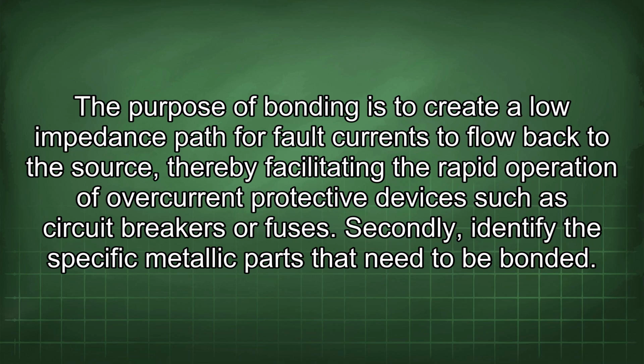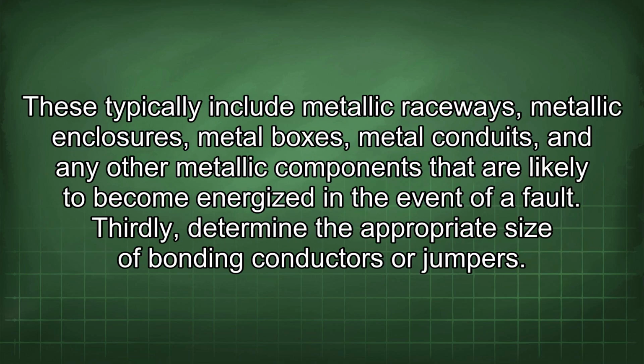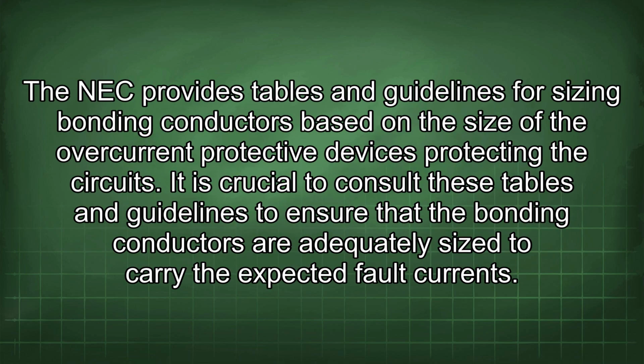Secondly, identify the specific metallic parts that need to be bonded. These typically include metallic raceways, metallic enclosures, metal boxes, metal conduits, and any other metallic components that are likely to become energized in the event of a fault. Thirdly, determine the appropriate size of bonding conductors or jumpers. The NEC provides tables and guidelines for sizing bonding conductors based on the size of the overcurrent protective devices protecting the circuits. It is crucial to consult these tables and guidelines to ensure that the bonding conductors are adequately sized to carry the expected fault currents.